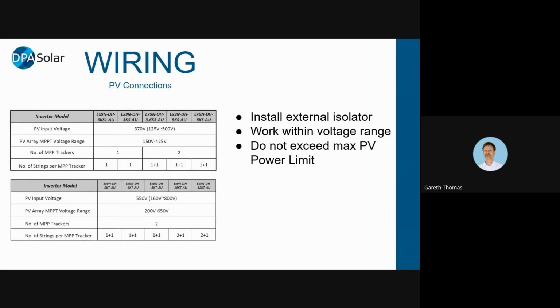As far as the PV wiring goes, it does have an isolator built into it, but it says in the manual you need to use an external isolator. And then depending on what state you're in, you'll probably need one up on the roof as well. You need to work within the PV voltage range of the inverter, just like you do with any inverter. You'll need to work within those voltage parameters. And you can see there's different numbers of trackers. So the 3.6, the 5, and the 6 in the single phase both have 2 trackers and 2 sets of inputs. And then on the 3-phase, there's also 2 trackers as well.